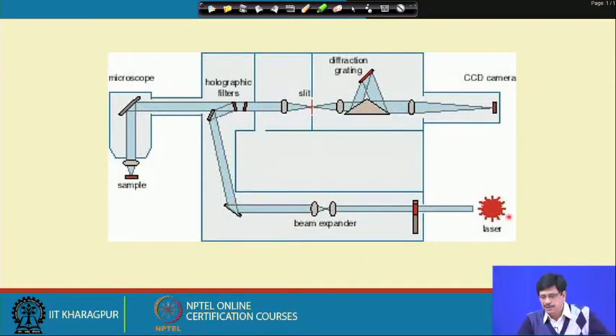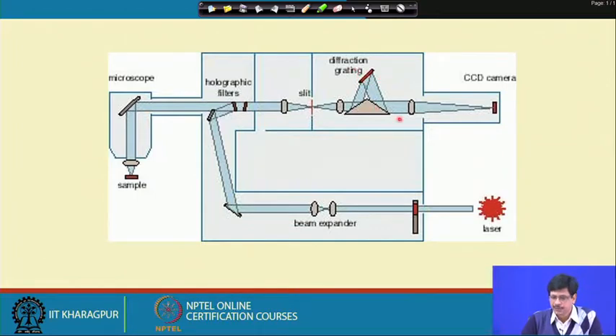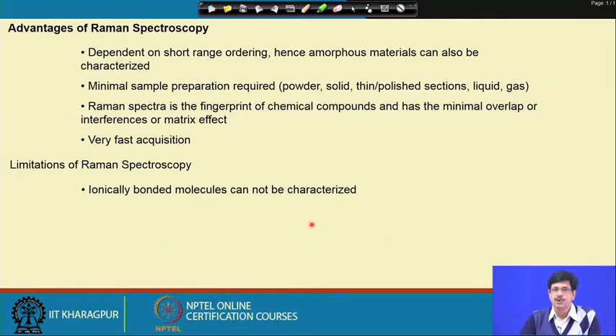The basic units of the laser Raman spectrometer are: the laser source (argon ion, solid-state, or other), the optics guiding it through the microscope objective onto the sample, a device to filter out Rayleigh scattering, a grating to disperse the emitted inelastically scattered light, and a detector that senses the intensity of each particular frequency. A key advantage of Raman spectroscopy is that it depends on short-range ordering, so amorphous materials can also be characterized.